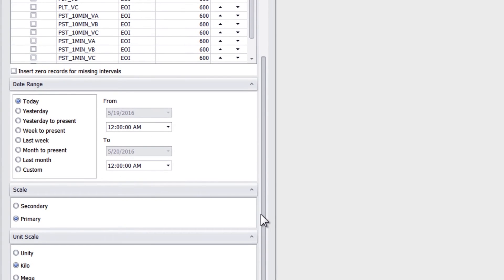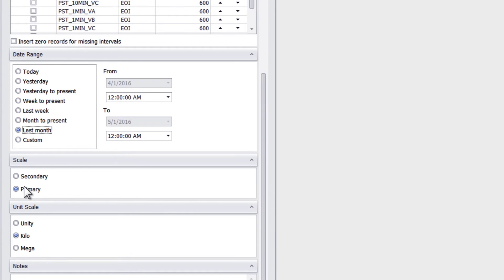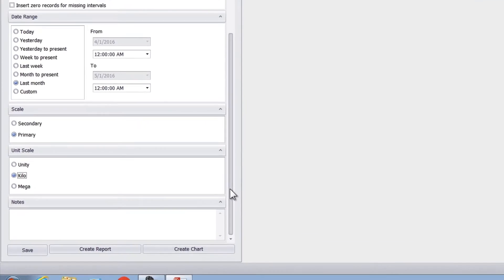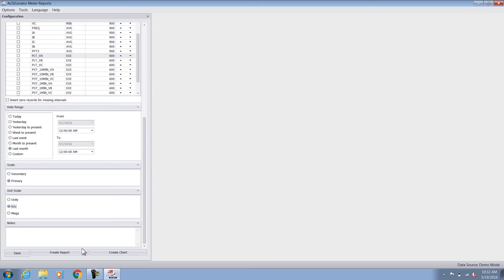Once I have the quantities selected, I scroll down and select a date range for this configuration. I'll select last month and for scaling, I can select primary and kilo. This can be different from the settings in the meter, which gives me more flexibility while creating the report to customize it for a specific application. Right at the bottom of this interface, there are two options: create report or create chart. The create chart option lets me interact with the data, which is the HMI version of it, and the create report creates a static report ready for printing.